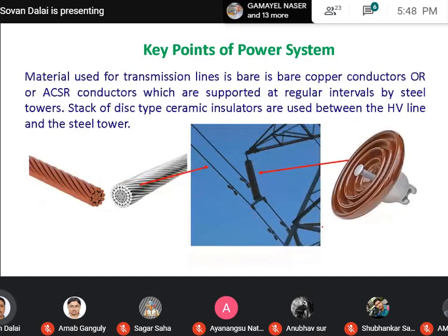And already I discussed that the material used for transmission lines is bare copper conductor or ACSR conductor. Nowadays, in most cases ACSR conductor is used because copper conductor is costlier compared to ACSR. And already I mentioned during the presentation that sometimes, to improve corona performance and also the power transmission capability, we use bundle conductors. As insulator, in most cases in India you will find porcelain, but if you go to Maharashtra, Pune, on that side you will find glass also used as an insulator. Nowadays porcelain and glass insulators are being replaced by composite insulators, in which we use polymer, that is silicon rubber, as the insulating material.